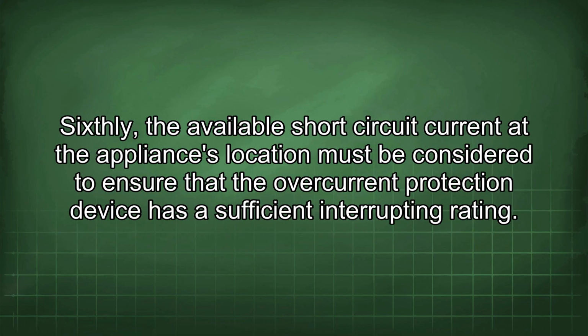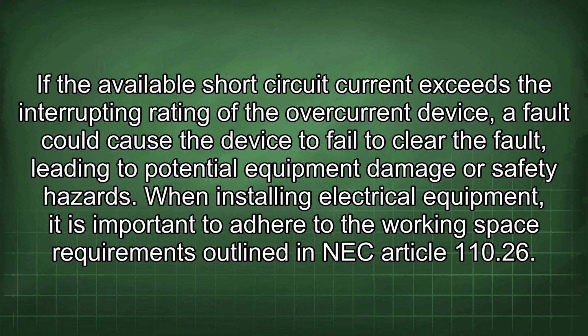Sixthly, the available short-circuit current at the appliance's location must be considered to ensure that the overcurrent protection device has a sufficient interrupting rating. If the available short-circuit current exceeds the interrupting rating of the overcurrent device, a fault could cause the device to fail to clear the fault, leading to potential equipment damage or safety hazards.